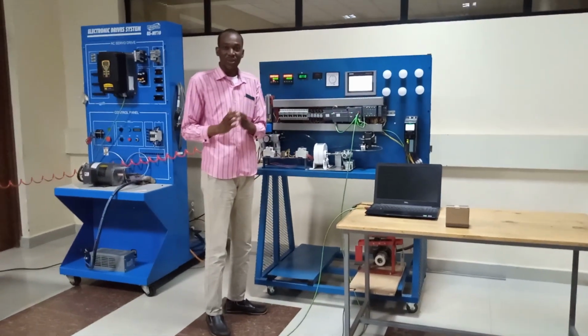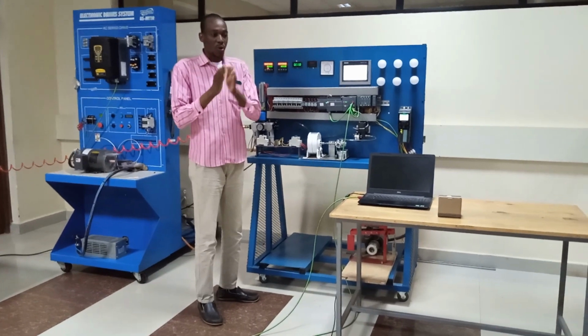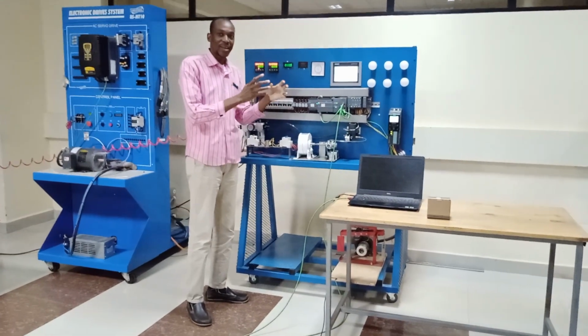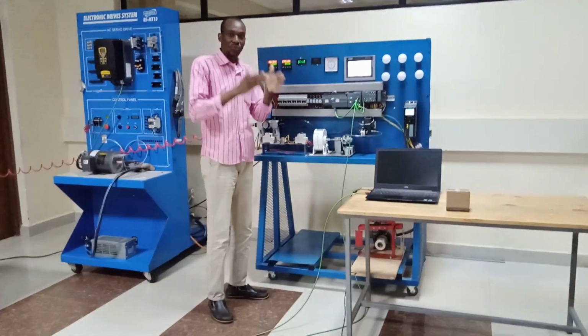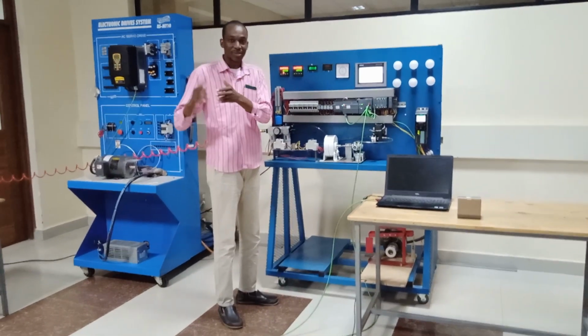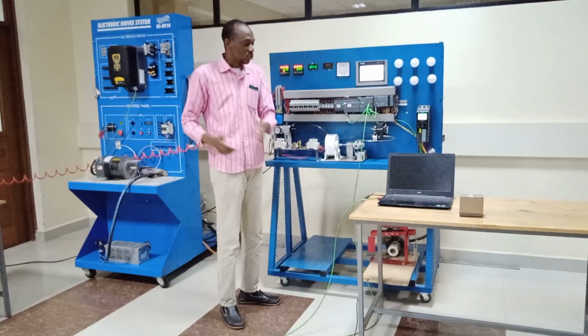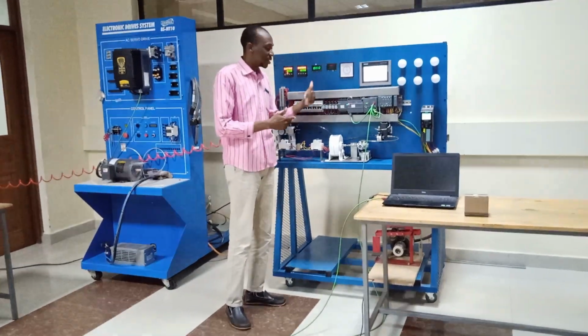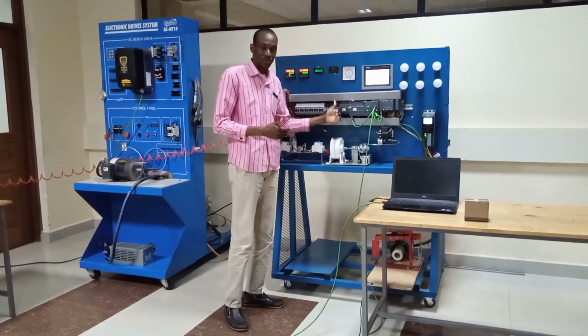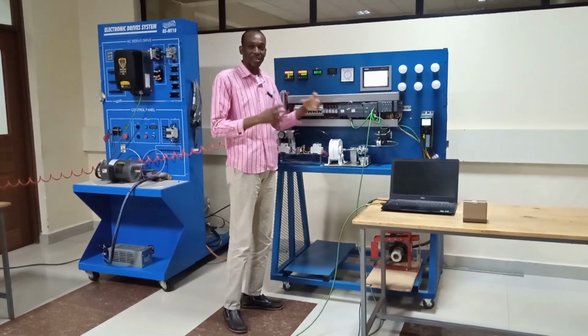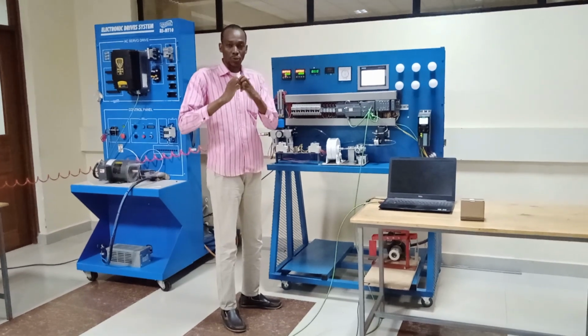And that IP converter is to convert this current, from 4 to 20 milliamps or 0 to 27,648, to a pressure. Then we will get a desired output pressure to the motor, to the turbine. Then this pressure is controlled.